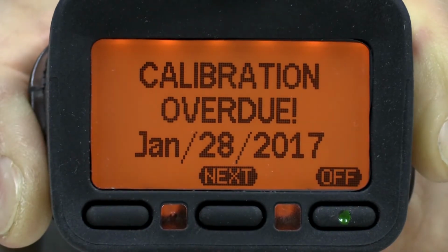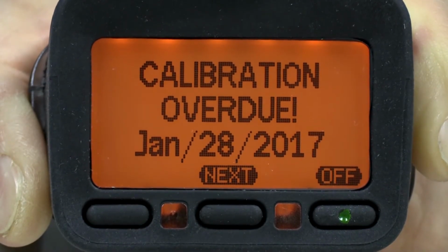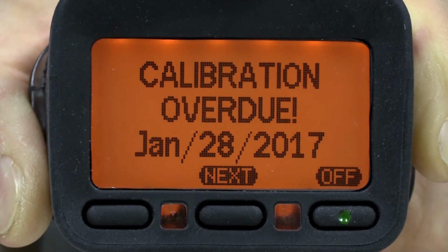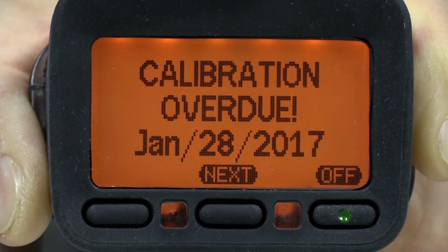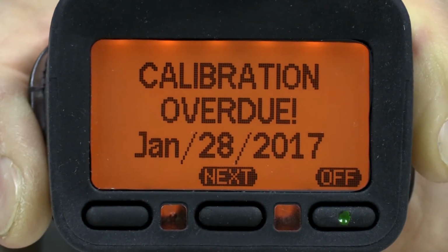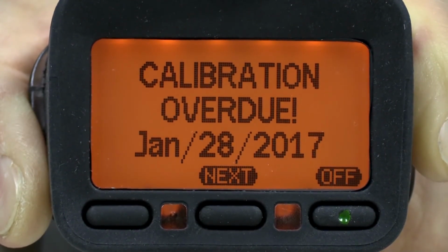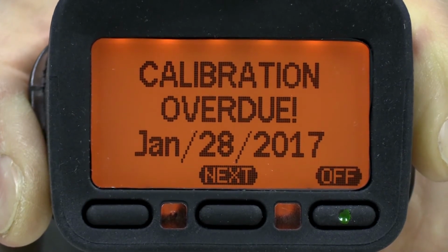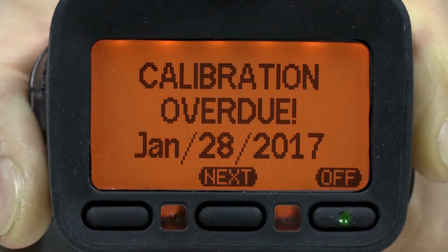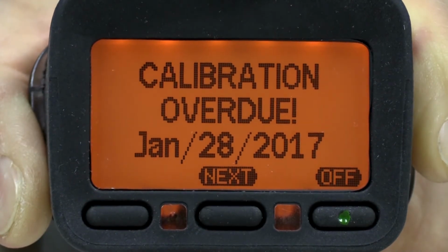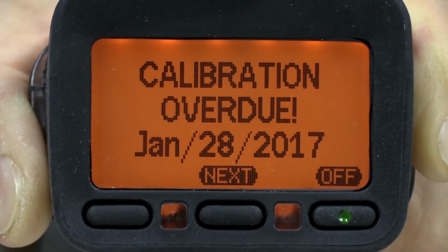A calibration overdue alarm is displayed if one or more of the sensors has not been calibrated by the required date. A calibration overdue alarm is also triggered by an unsuccessful attempt to calibrate or fresh air adjust the instrument. The alarms will continue to be displayed every time the instrument is turned on until they are cleared by performing the required procedure.